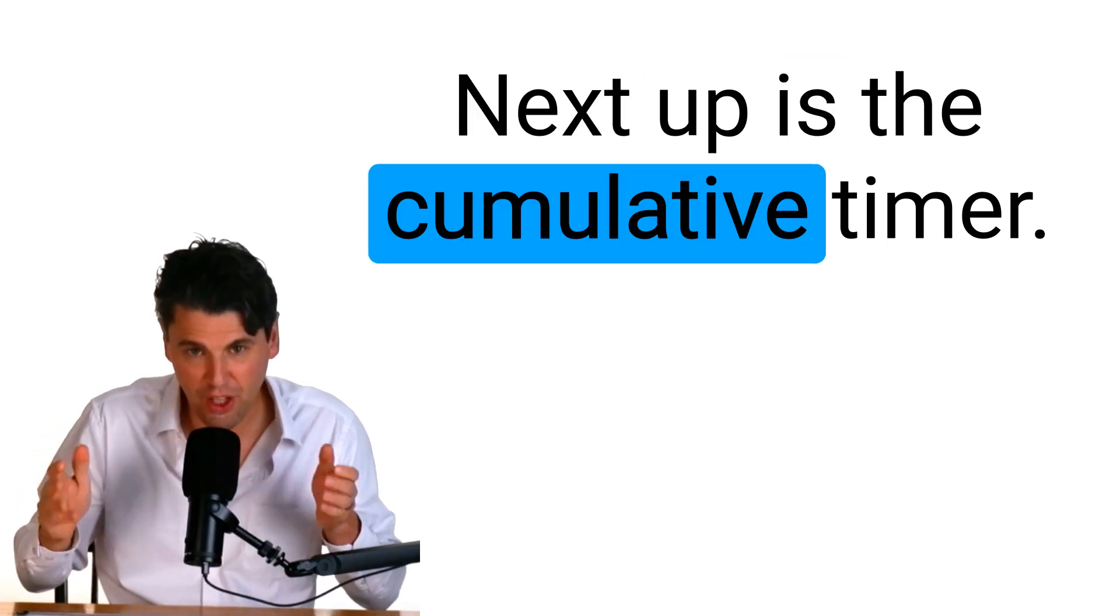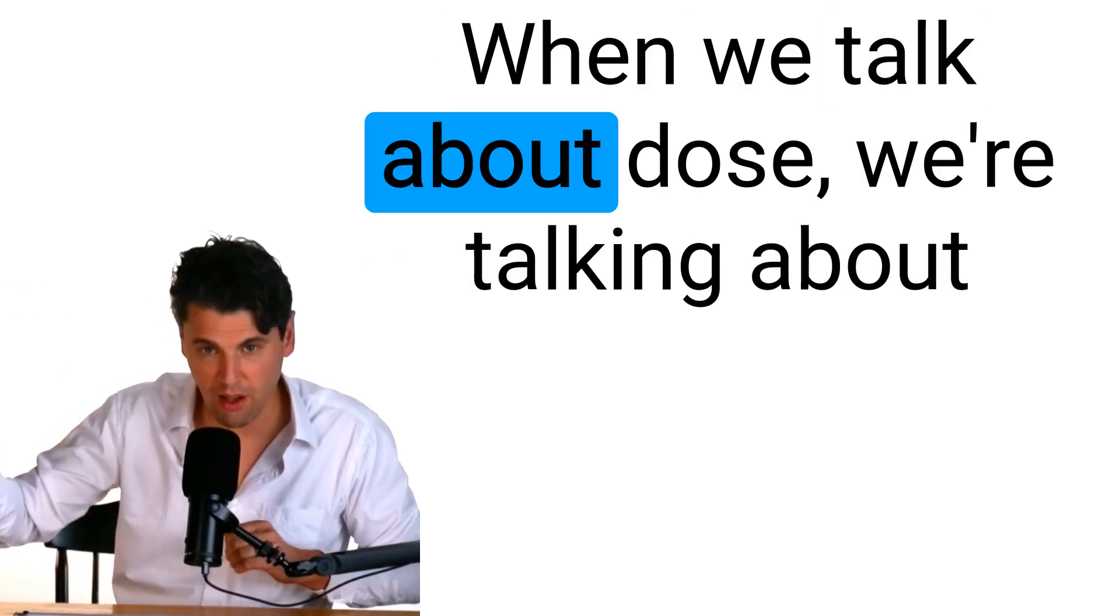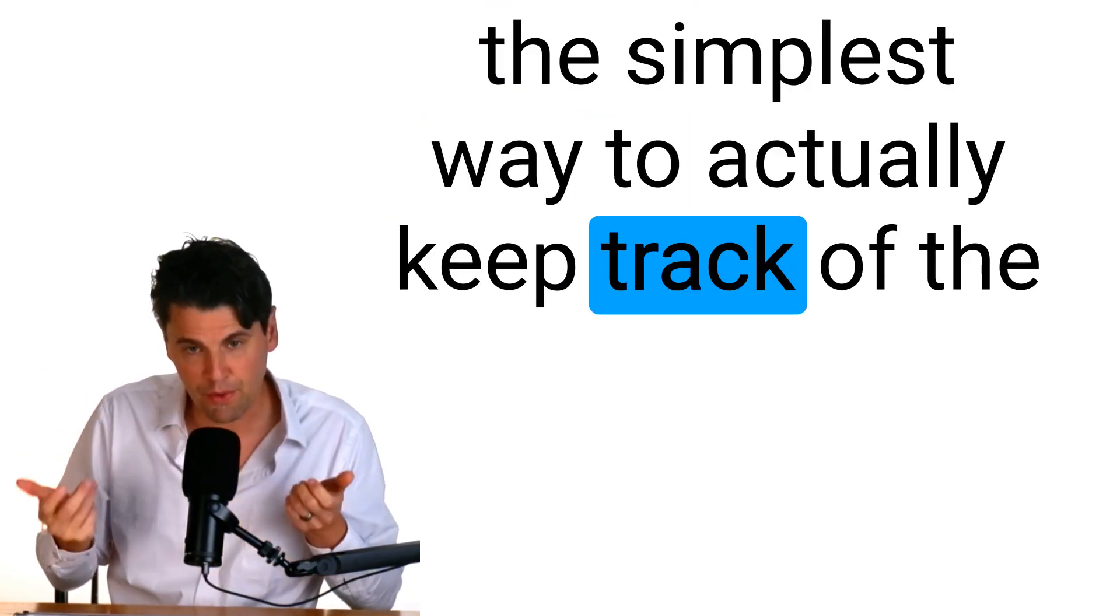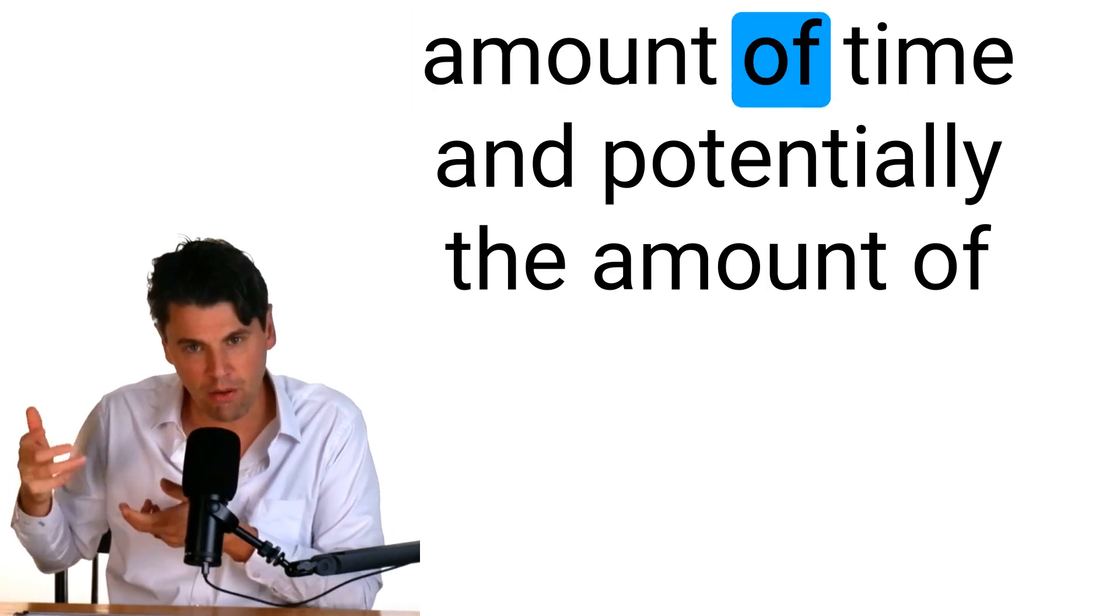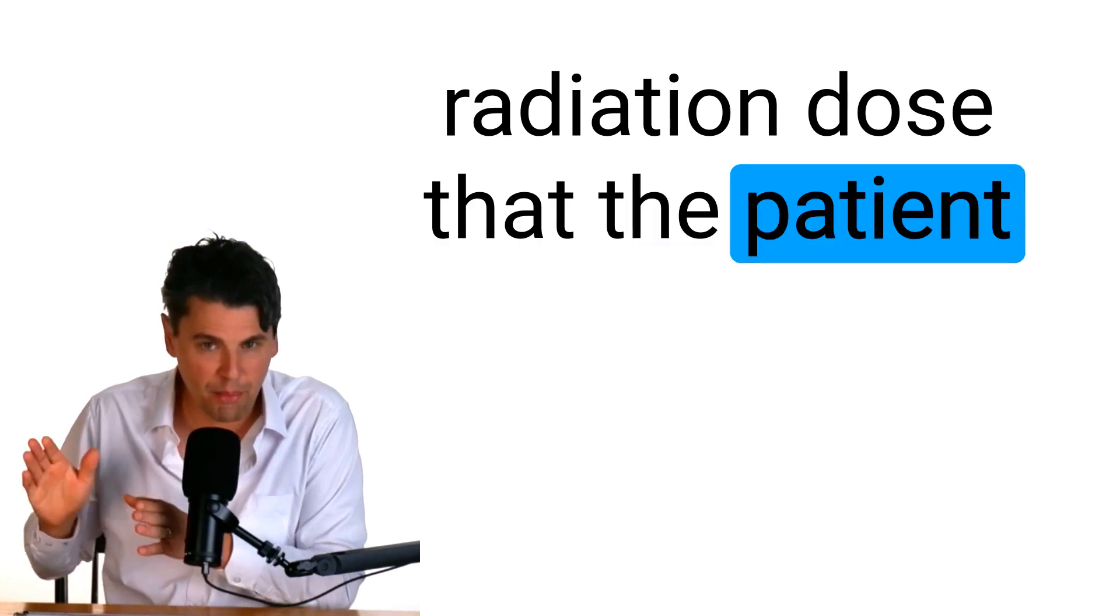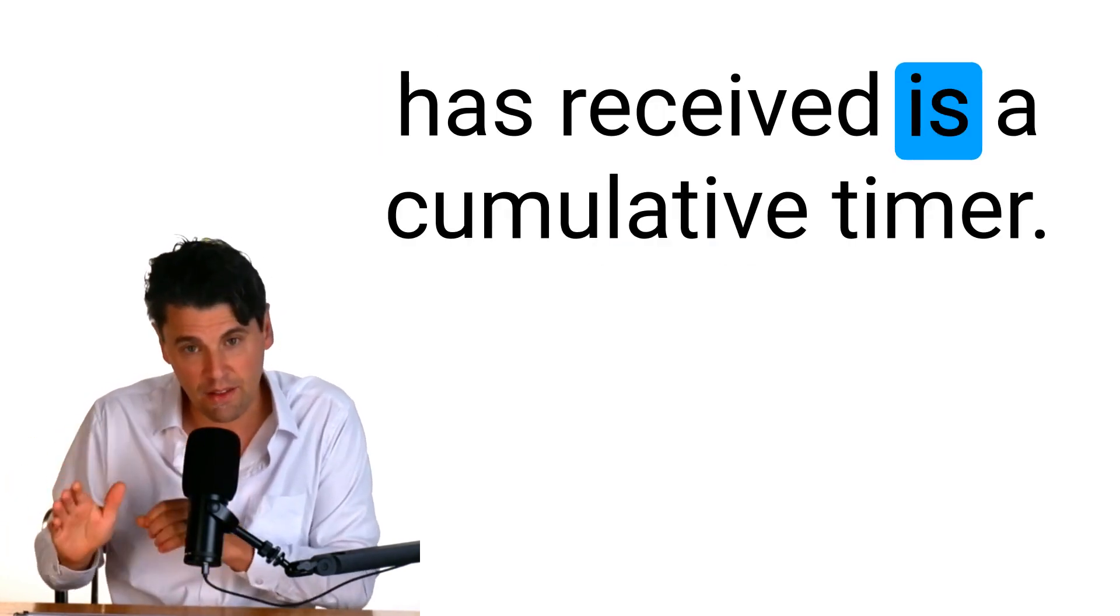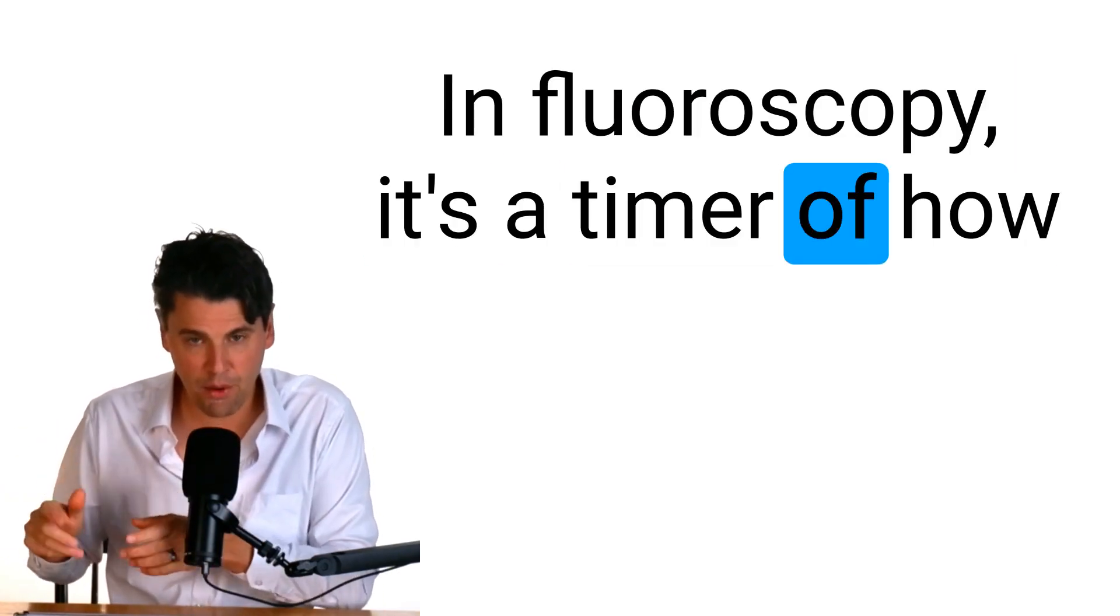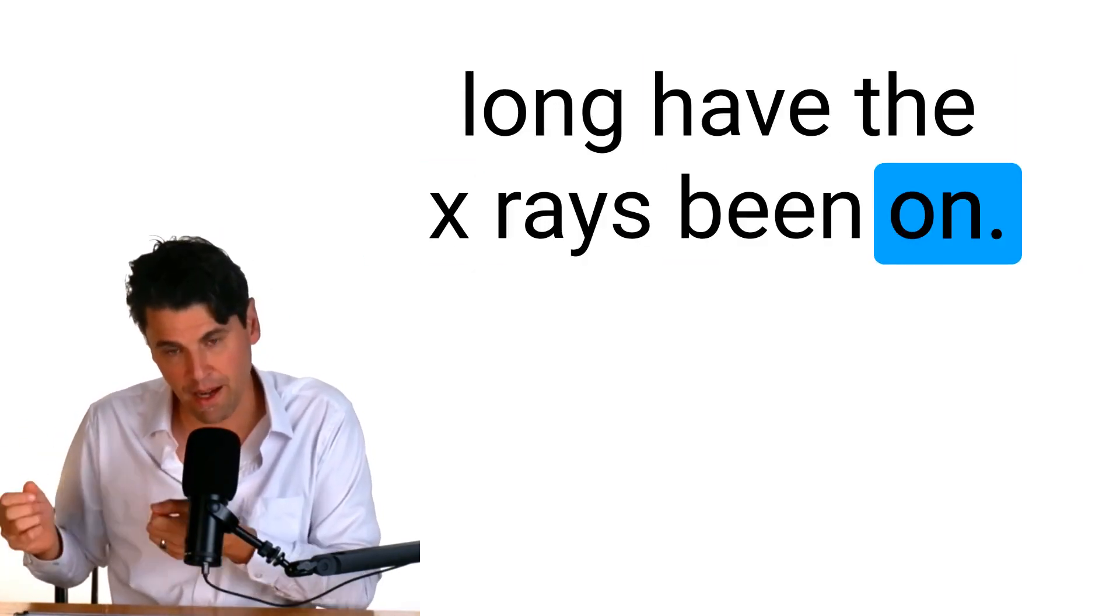Next up is the cumulative timer. When we talk about dose we're talking about the simplest way to actually keep track of the amount of time and potentially the amount of radiation dose that the patient has received is a cumulative timer. In fluoroscopy it's a timer of how long have the x-rays been on.